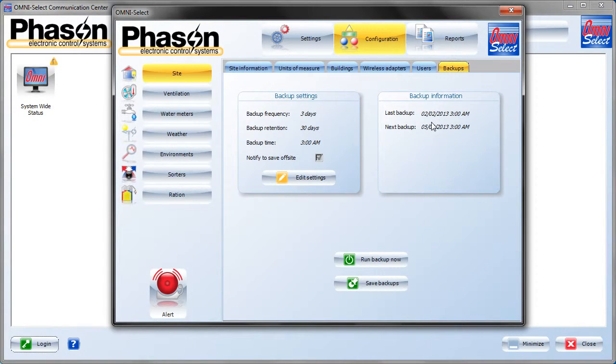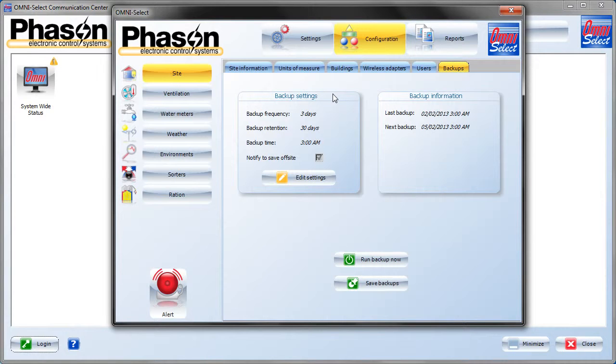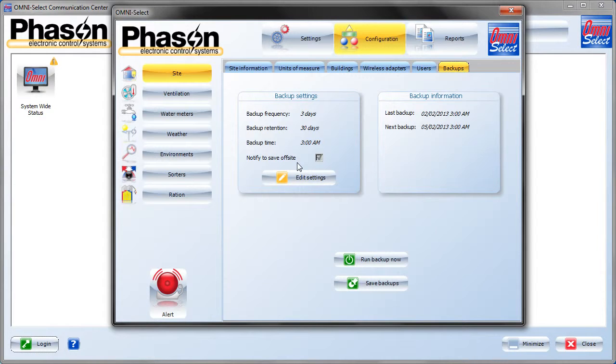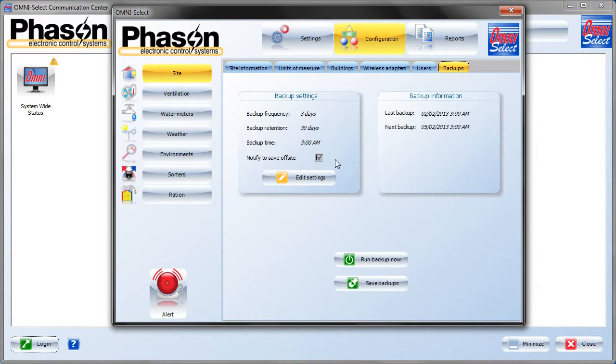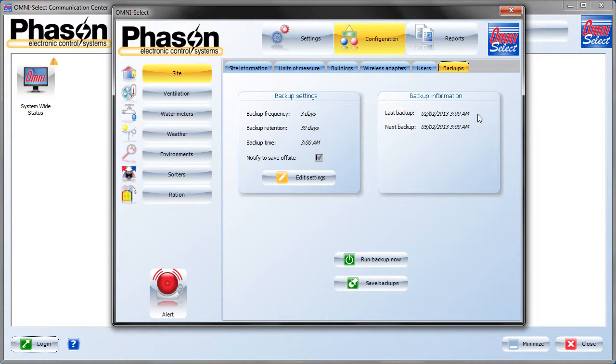In the Backups tab, the Select system automatically performs a complete backup containing all the settings, the configuration, and the report data. Those settings are in here. You can change how and when and how often it performs a backup under the backup settings, and also how long to keep that backup. For notify to save off-site, you can choose to have it post a reminder in the communications center to copy the backup file off the computer in case it crashes. It will automatically do a backup at these times and dates, but it's up to you to make sure that you copy that backup file off-site to an external drive, preferably like a USB stick that you can take off-site in case something catastrophic happens in the building.